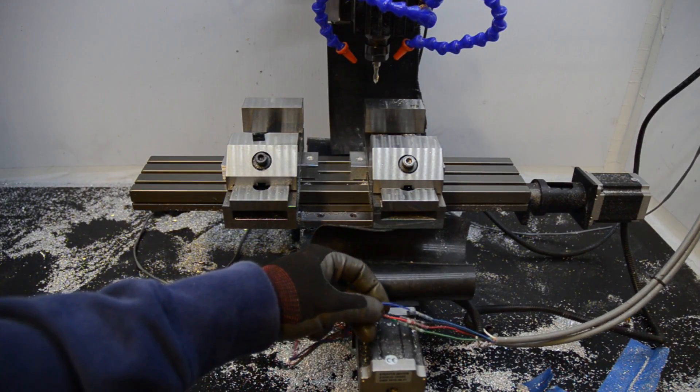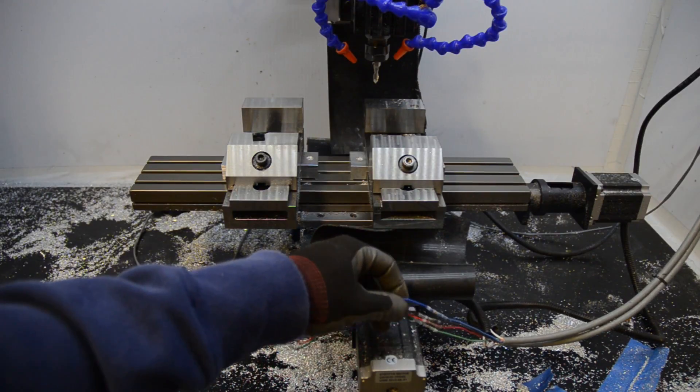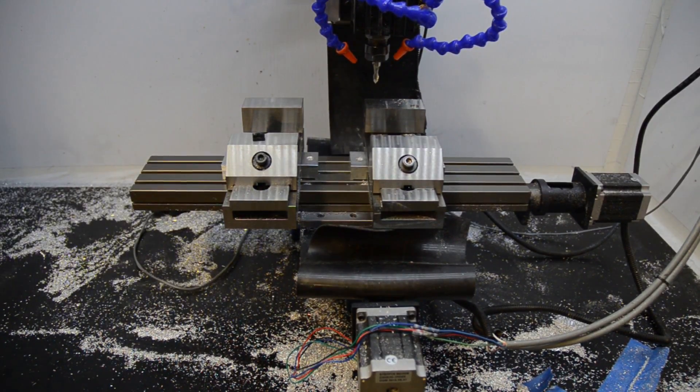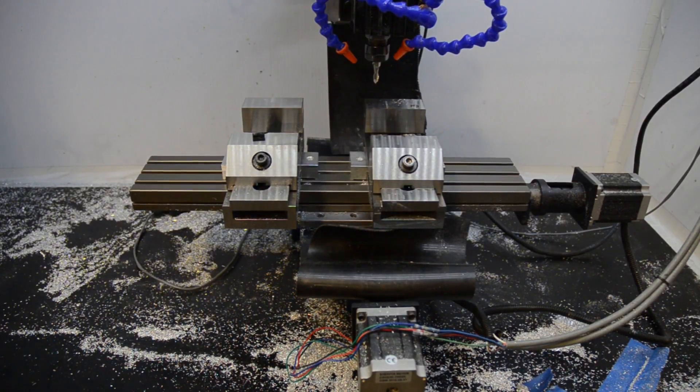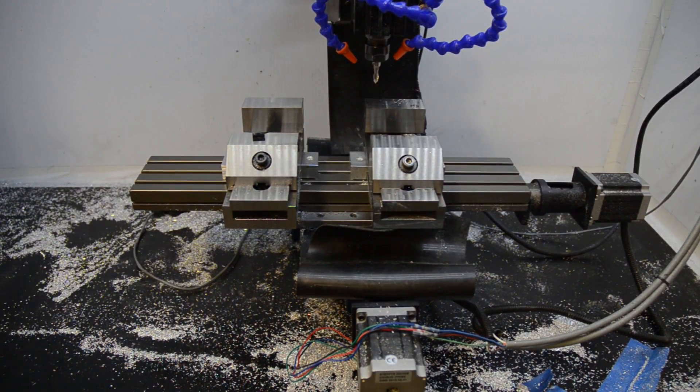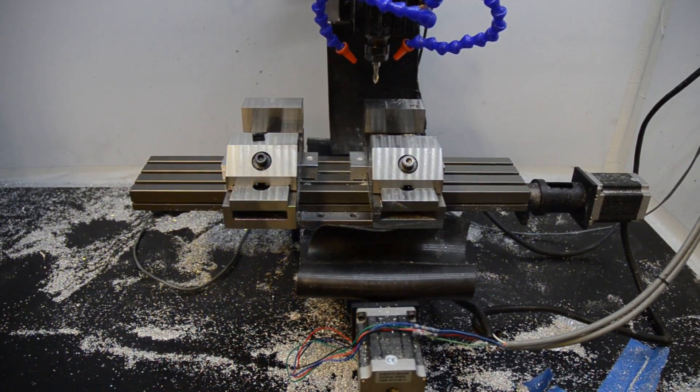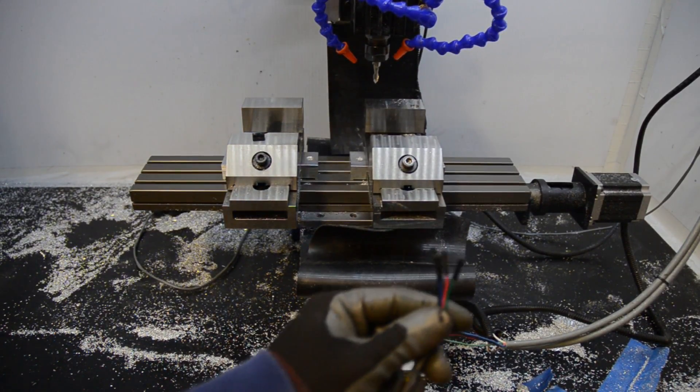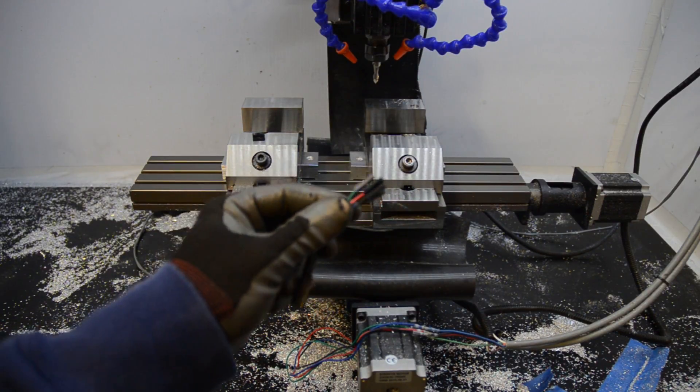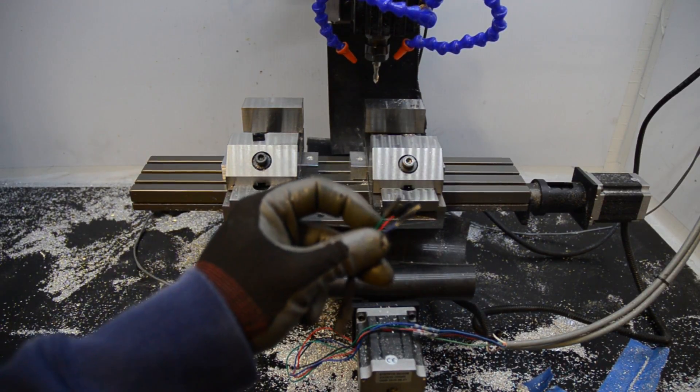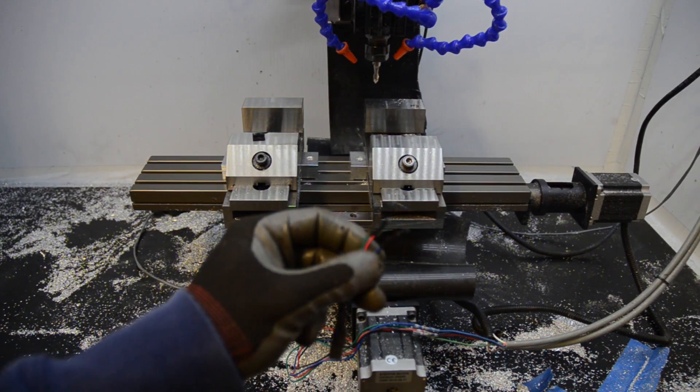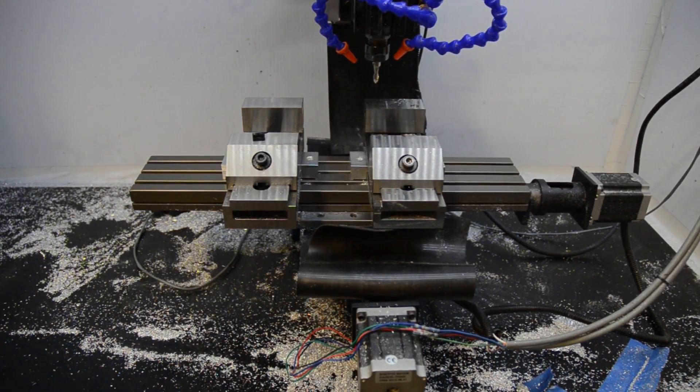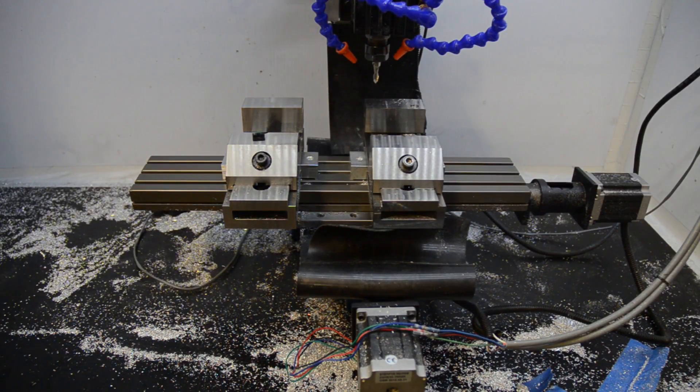You don't want to go with a small wire because you are actually moving a fair amount of current for a very long amount of time. Sometimes I've run this for six to eight hours non-stop on a long operation and the wires will get very hot, and on these kinds of connectors I've had problems with them melting. Not all the way through melting, but they have softened and they've actually stuck together. Don't go with a poor mechanical connection. Get a really good mechanical connection and make sure you're not using too thin a wire.